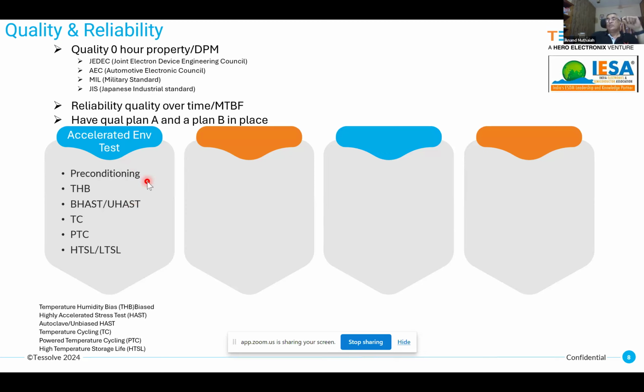In preconditioning, before you start your qual tests, we need to bring the device to a nominal mode, meaning the MSL mode - the moisture sensitivity level should be set before you start any of these tests. There is a JEDEC spec for all of this moisture sensitivity level. Normal consumer product is moisture sensitivity level 5.